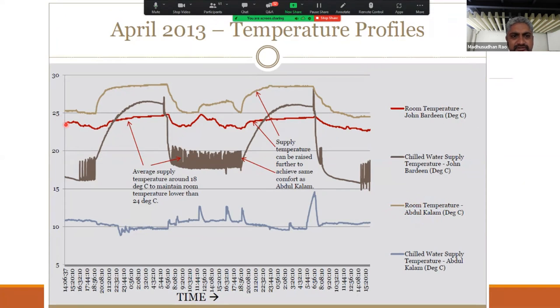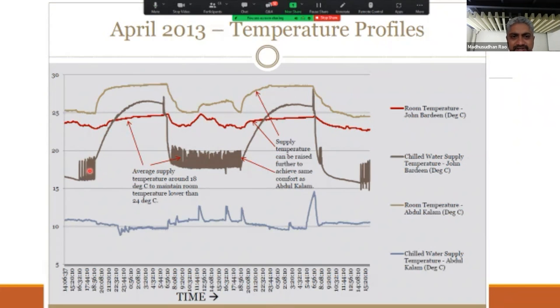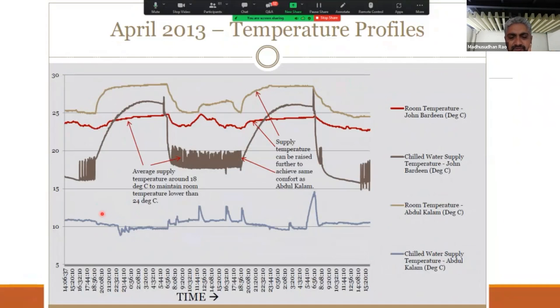So this is the temperature profile over 2-3 days of this room, which is with AHU. The red color is the space temperature profile of the space, which was done with radiant. This is the supply temperature to the radiant system. This is the supply temperature to the air handling unit. Okay. Now, what you will observe, and this is one thing that we really need to understand about how radiant cooling systems work. What you're saying is right. It is not an instantaneous on and off.